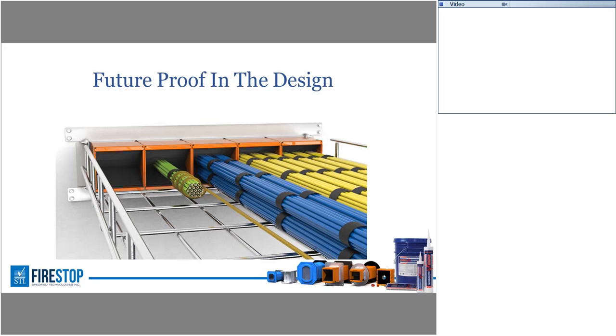Cable pulls. So if we're very, very careful about how we design the building or a part of the building, and we know that we've got multiple barriers, if we're using EZ-Path and we're ahead of the game on this by leaving pull strings within those EZ-Path, you could eliminate popping ceiling tiles at every single barrier. You could actually pull cable over a distance over multiple fire-rated assemblies without ever popping the ceiling tile. So think about the labor savings, think about infection control issues, all those things that can be achieved by doing this. It's a planning application, I get it, but we use this in many facilities and it works well.